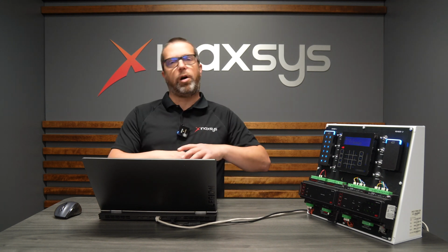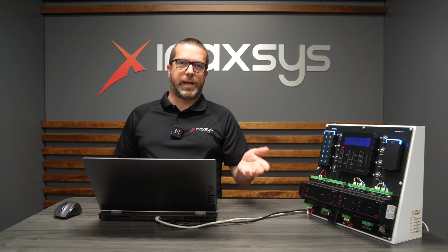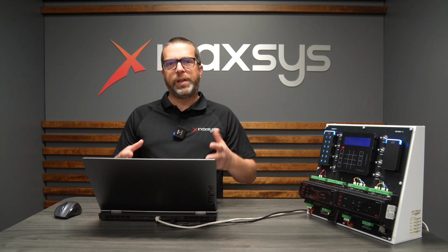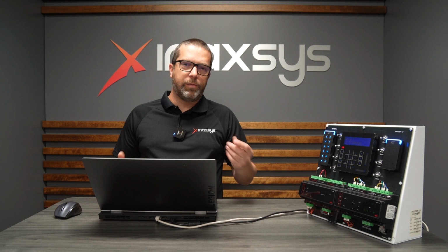The main difference is, with the basic version of elevator control, you badge your card and all the floor relays will activate. So there is a possibility of someone behind me or inside the cab with me pressing one of the floors I have access to without having to badge inside the cab. Destination reporting will invert the way it works by default. Now when I badge my card, I have to make a floor selection and then only that floor relay will trigger. There's only one floor that I can select. I cannot select multiple floors.